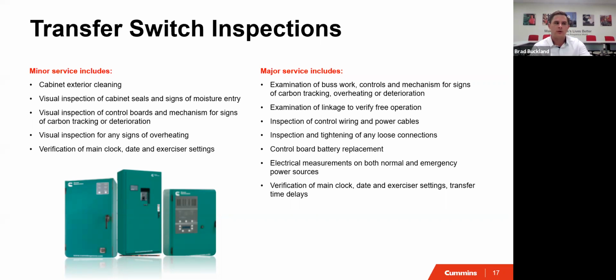There's a standard we have to operate off of for these called an arc flash assessment. If you have a newer ATS unit, it should have had this done by the electrical contractor during the original assessment. Really, it's a sticker telling you how dangerous and how much incident energy is behind that ATS. For 30 years, technicians in the field were opening and closing these things with no problem, then one or two issues occurred, which sparked a lot of change within the industry. So even if you aren't servicing these, make sure there's an arc flash sticker on there that tells you how much energy is behind it, with a rating in calories.